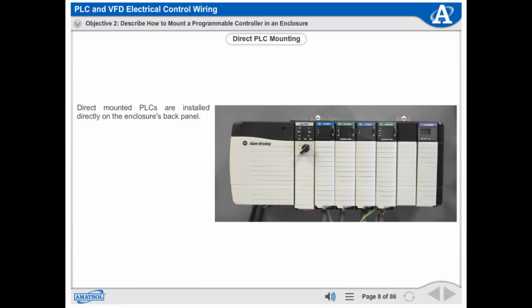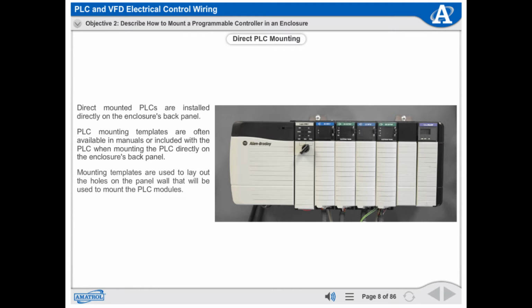Direct-mounted PLCs are installed directly on the enclosure's back panel. PLC mounting templates are often available in manuals or included with the PLC when mounting the PLC directly on the enclosure's back panel. Mounting templates are used to lay out the holes on the panel wall that will be used to mount the PLC modules.